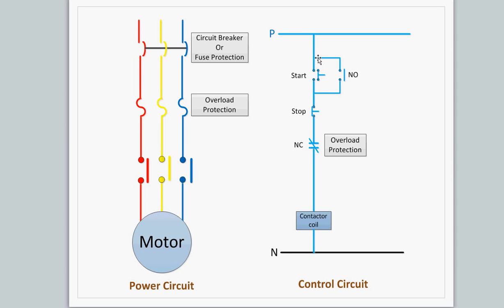In the control circuit, you can see here, when the operator presses the start button, the circuit closes and the contactor is activated, and at that time it closes all these three contacts here. Once the operator releases the start button, the current continuously flows through this normally open contact of the contactor, but once it is activated, this contact gets closed and now the circuit will flow from this side here.